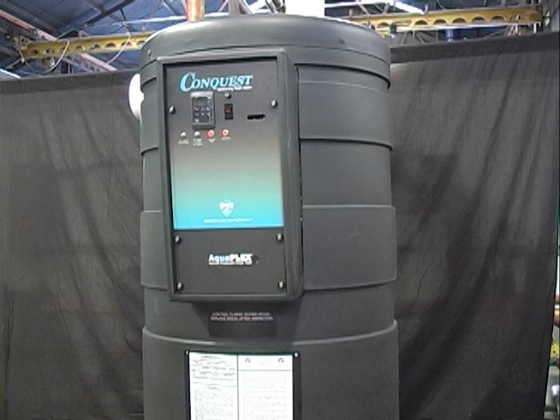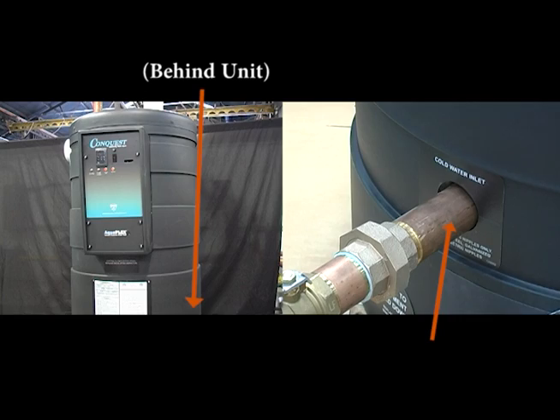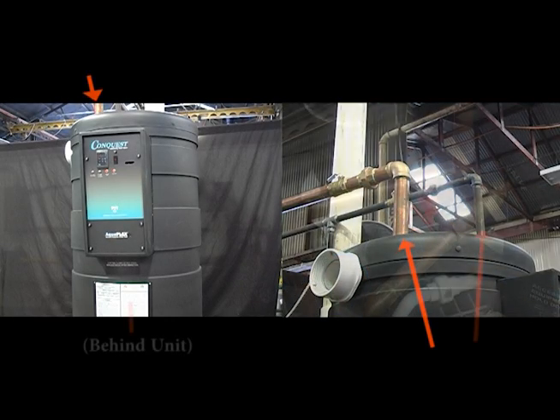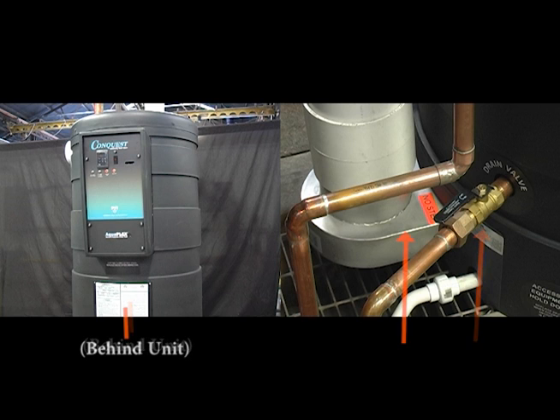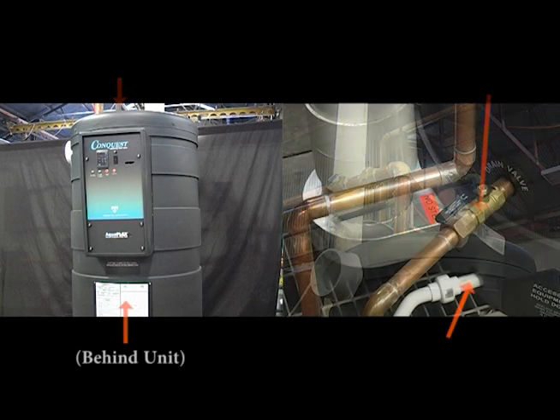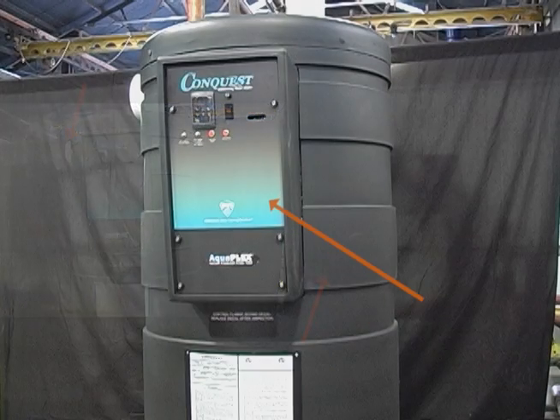Before commissioning the Conquest water heater, it is important to ensure the installation is complete and that all connections are made to the water heater in accordance with the guidelines and requirements detailed in the installation and maintenance manual supplied with the product. These necessary connections are the cold water inlet, the hot water outlet, the tank drain, the vent connection, the gas inlet, the condensate drain, the combustion air inlet, and the electrical wiring to the control panel.